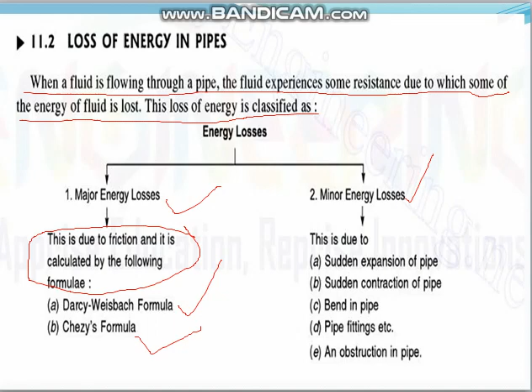First one is the major energy losses due to friction, which is given by the equation called the Darcy-Weisbach equation. Here the Darcy-Weisbach equation is given as head loss due to friction, hf, which is equal to f L V square by 2 g D. Here f stands for friction factor, which is a function of Reynolds number and relative roughness.